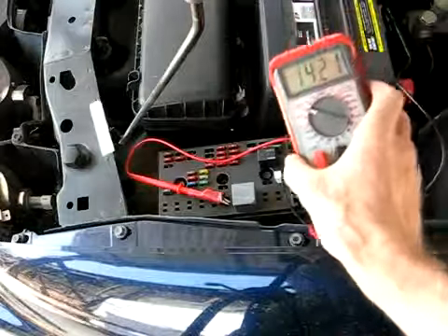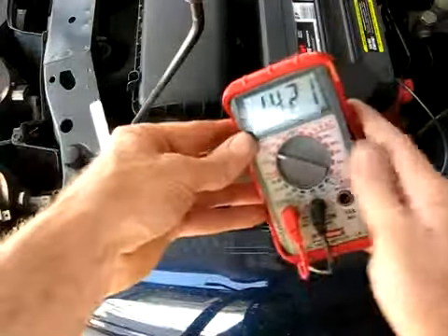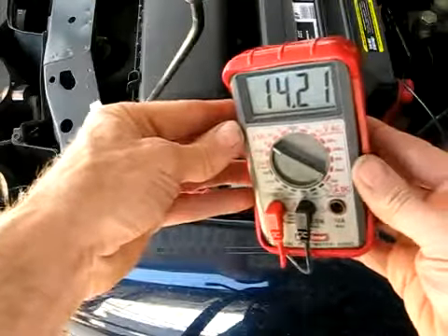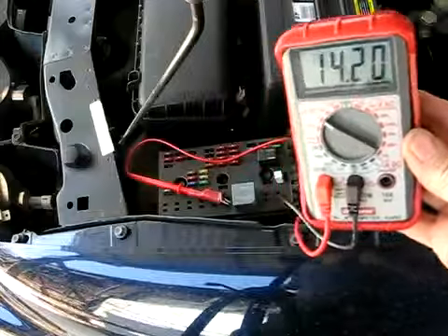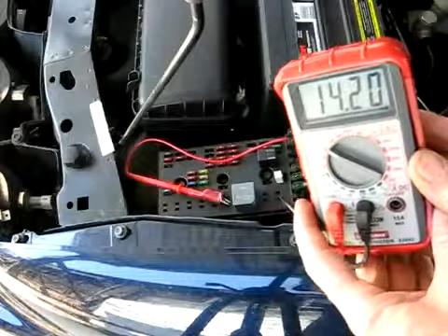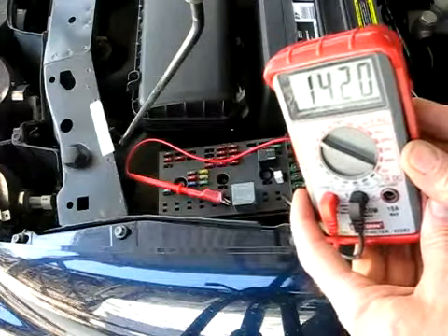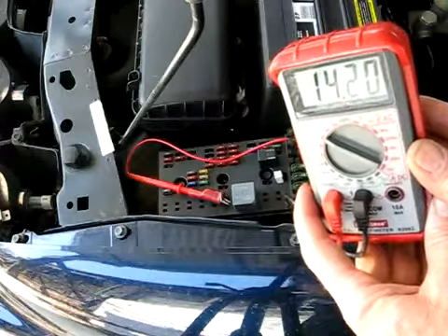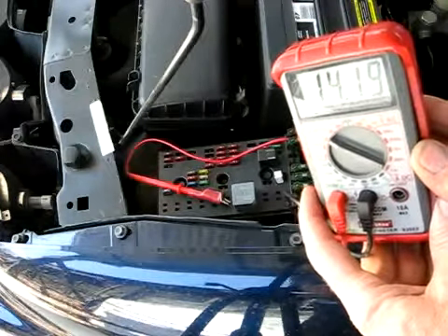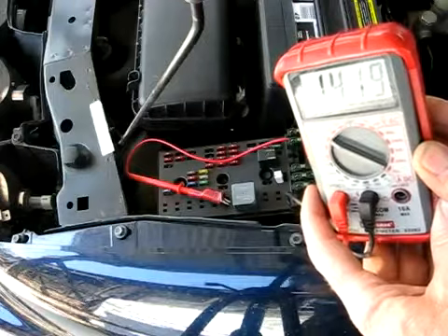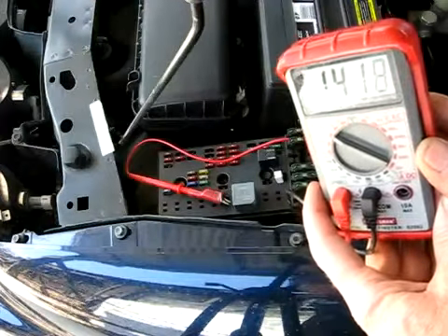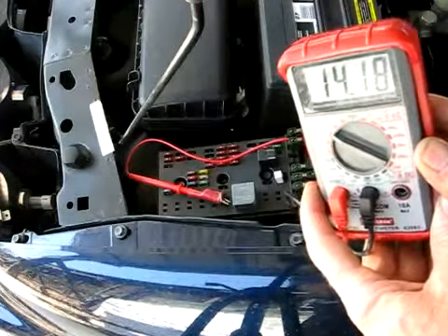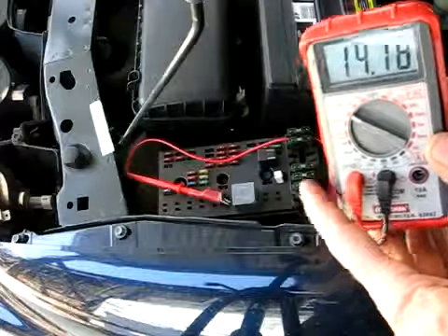Now if it's working correctly, you'll see voltage there at number 85. If you don't see voltage there, you want to check the ignition 3 fuse, the IGN 3 fuse. It's a 10 amp fuse located in the interior junction block. So check that.